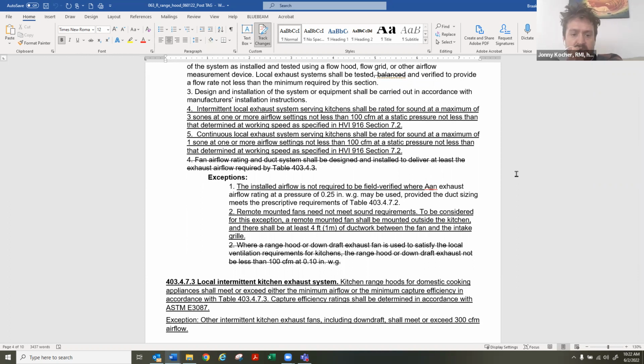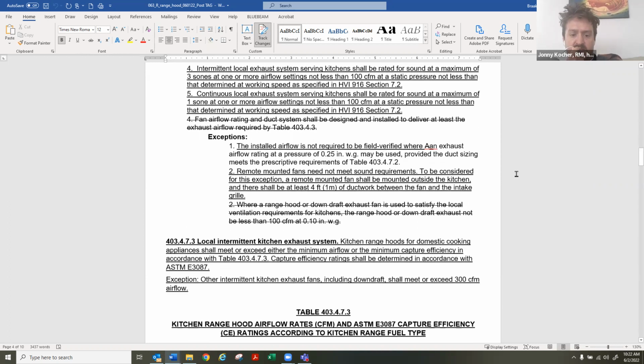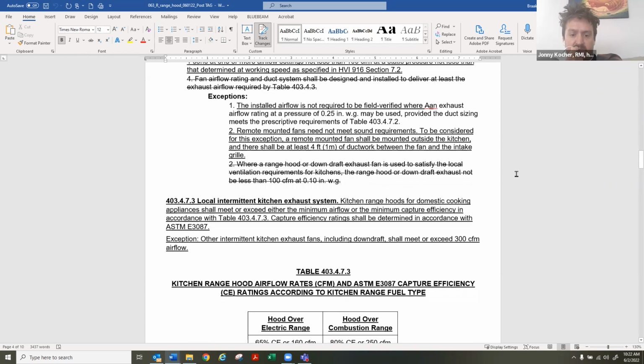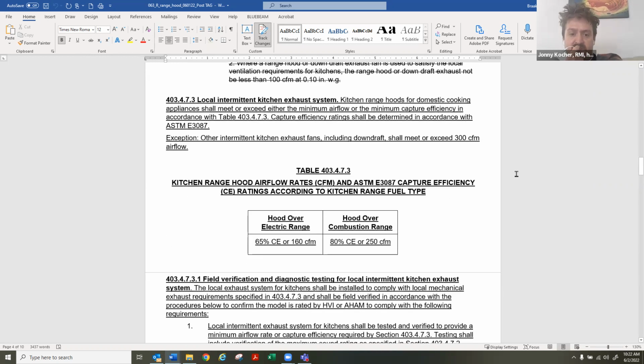And then for the actual exhaust requirements, we simplified the table for 3.7.3 based off of concerns we heard. So it is no longer based off square footage. Now it's just based off of fuel type, so it's either combustion range or electric range. And we simplified it to 250 CFM and 160 CFM, versus before we had it up to 280 on the combustion side, and it was based off square footage. We think the simplification would make it easier for it to be enforced.